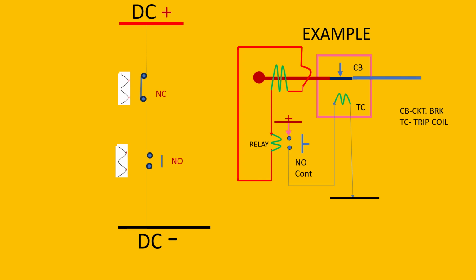In the control circuit we are using two sets of contact. One is normally closed, meaning when the magnet is de-energized, the contact which is in closed condition is normally closed. And in de-energized condition, the contact which is in open condition is normally open. The main thing is the de-energized condition. But when the magnet is energized, this normally open contact will be closed. So these two types of contacts we are using.